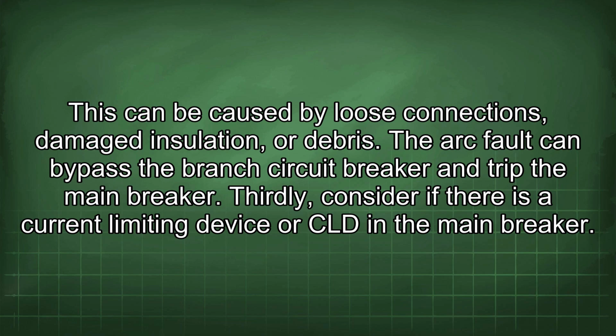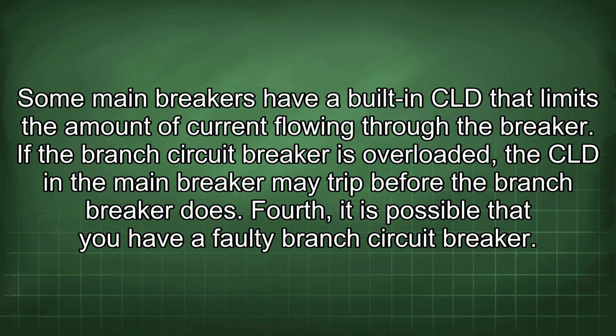Thirdly, consider if there is a current limiting device or CLD in the main breaker. Some main breakers have a built-in CLD that limits the amount of current flowing through the breaker. If the branch circuit breaker is overloaded, the CLD in the main breaker may trip before the branch breaker does.